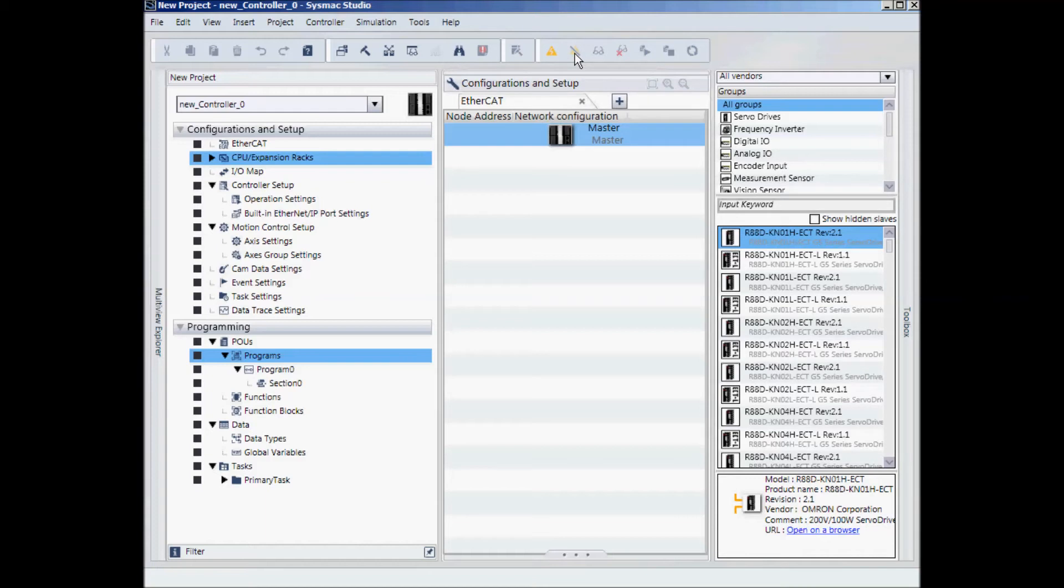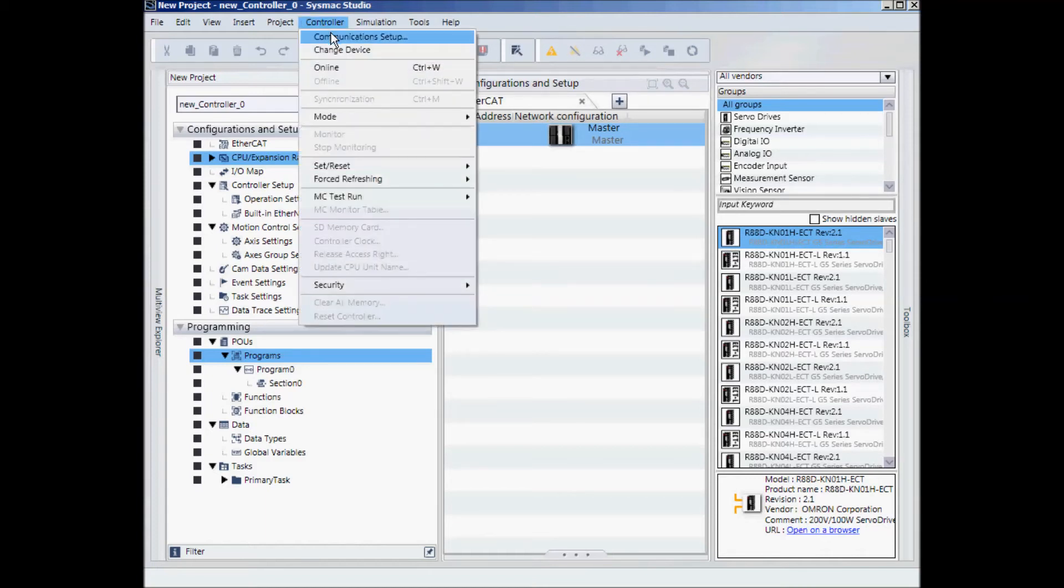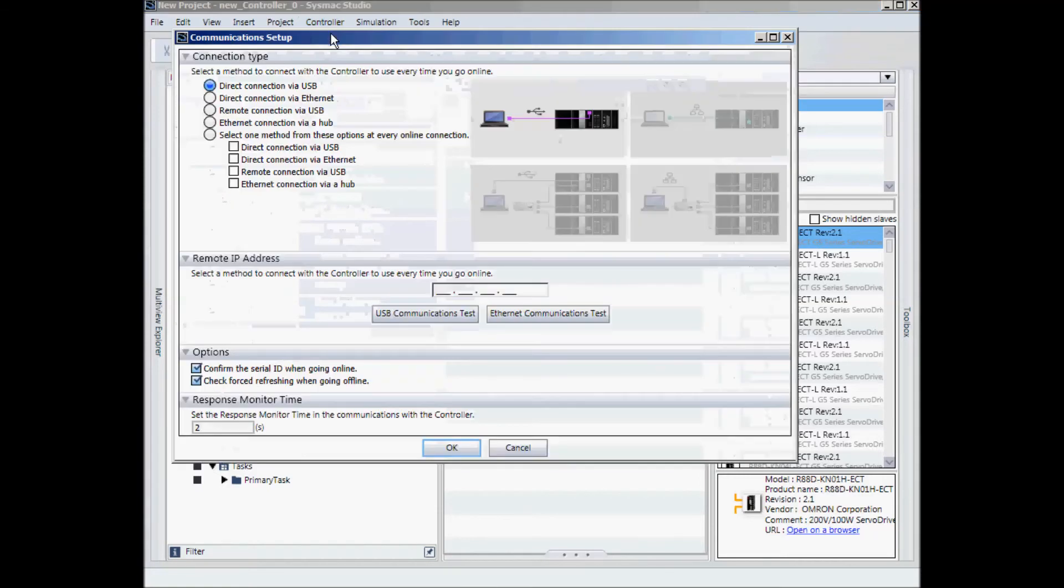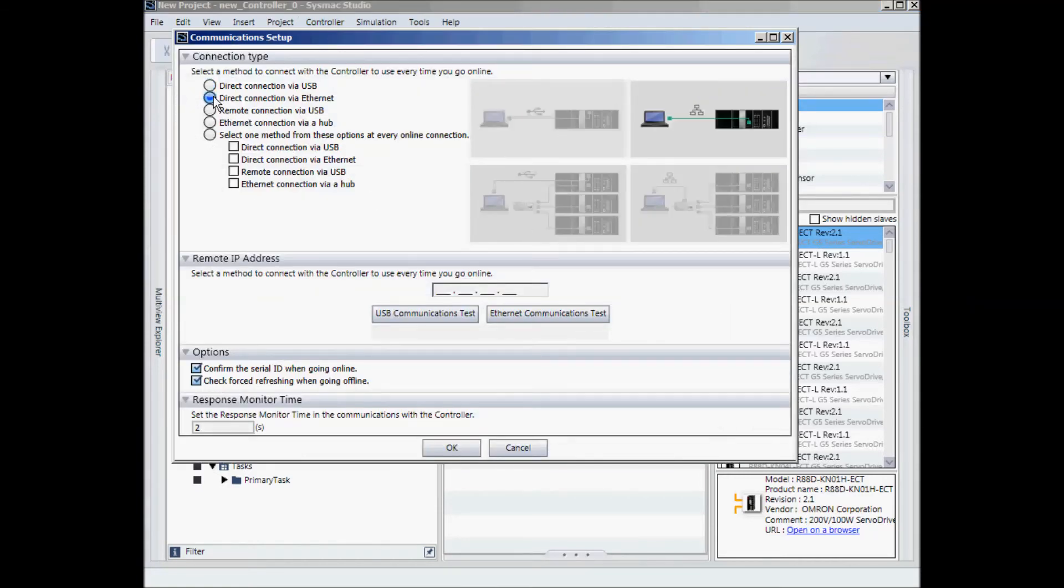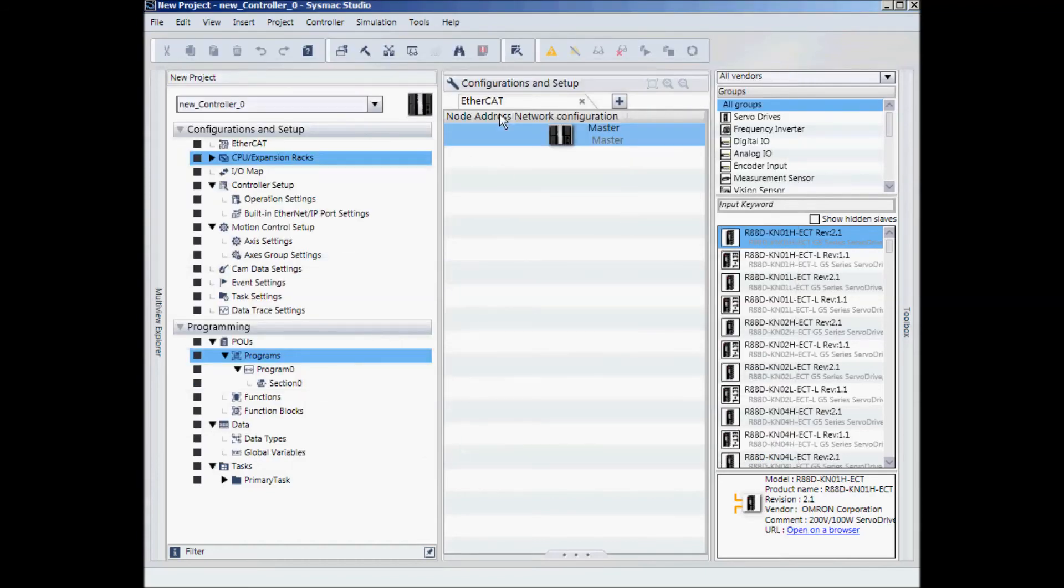This time I will connect over Ethernet. I will go to Controller, Communication Setup. I will select Direct Connection via Ethernet and I will type in the address of my controller, 192.168.250.001. I will now click OK.